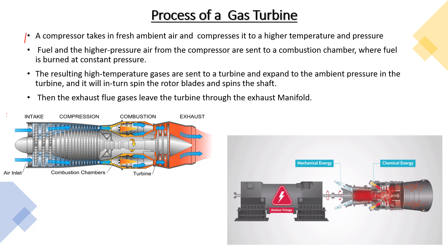The working principle has three steps. First, the compressor takes in fresh ambient air and compresses it to a higher temperature and pressure. Second, fuel and high-pressure air from the compressor are sent to the combustion chamber, where fuel is burned at constant pressure. Third, the resulting high-temperature gases are sent to the turbine, expand to ambient pressure, and spin the rotor blades and shaft.